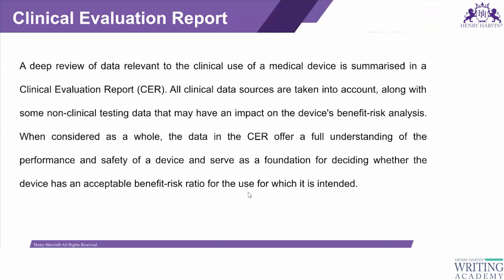All clinical data sources are taken into account along with some non-clinical testing data that may have an impact on the device risk benefit analysis. When considered as a whole, the data in the clinical evaluation report offer a full understanding of the performance and safety of a device and serve as a foundation for deciding whether the device has an acceptable benefit risk ratio for the use for which it is intended.